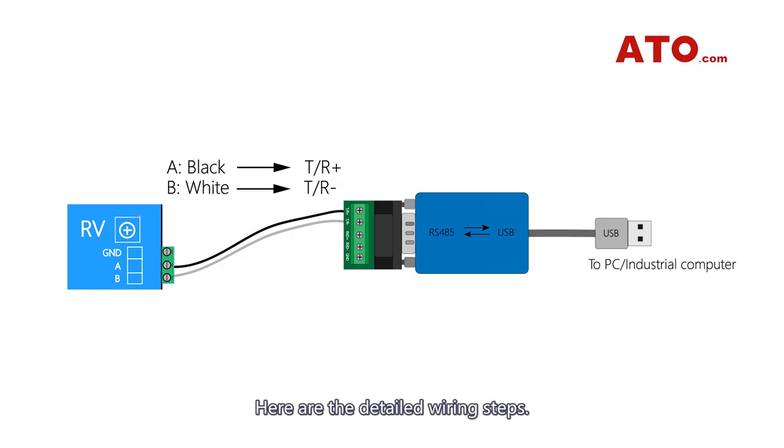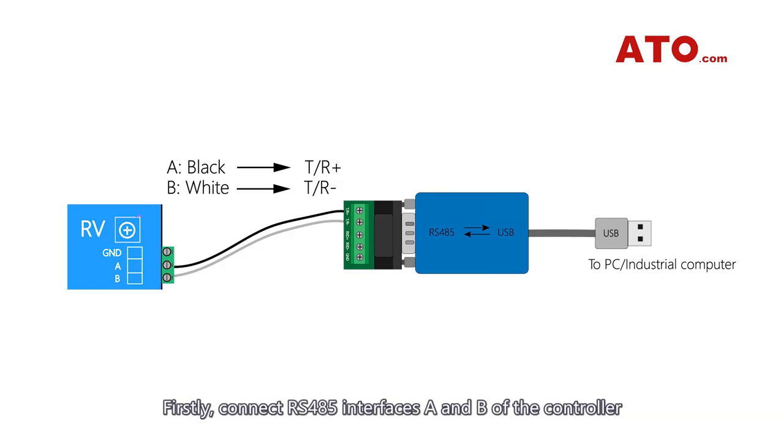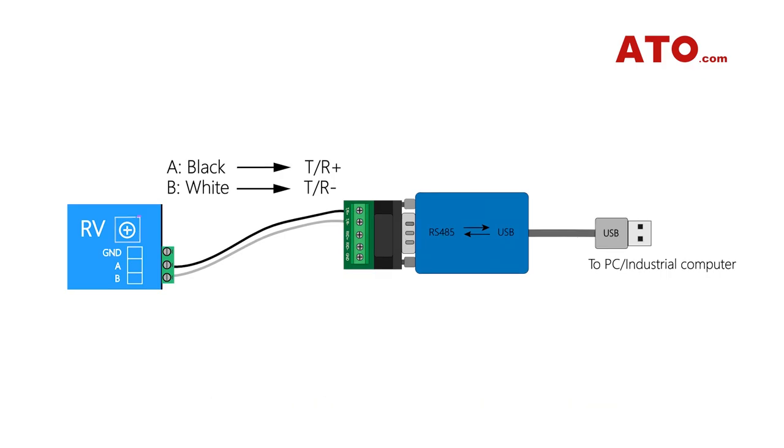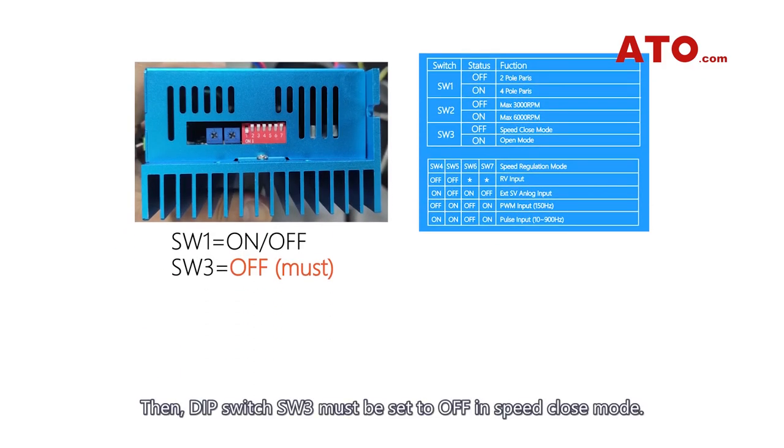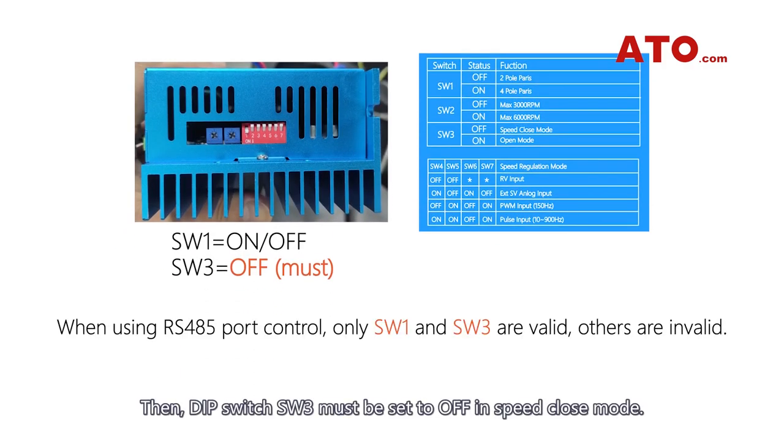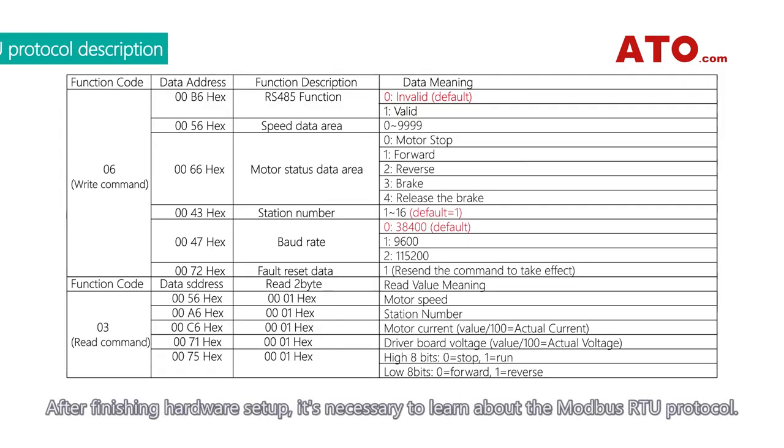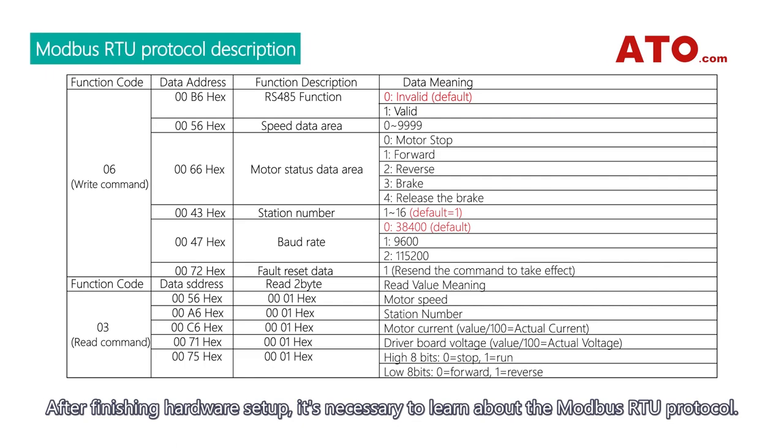Here are the detailed wiring steps. Firstly, connect RS485 interfaces A and B of the controller to T/R plus and T/R minus of the conversion module respectively. Then, DIP switch SW3 must be set to off in speed close mode. After finishing hardware setup, it's necessary to learn about the Modbus RTU protocol.